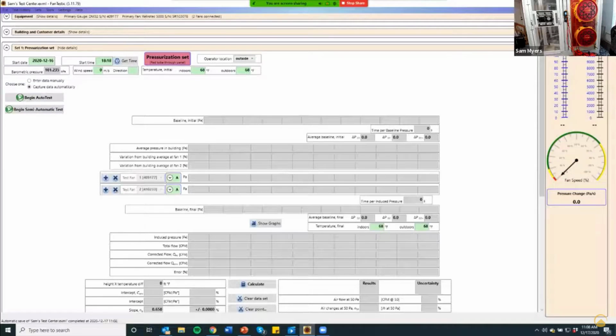Sometimes if you run an auto, just straight auto, it'll try to get down kind of low, and then sometimes that data won't be as good, and it'll show up as a red number. If I do it in semi-auto, I can just avoid that altogether. So it just gives you more control. Basically, most people who run these tests in the field choose the semi-automatic tests just so you can customize however you want to do it.